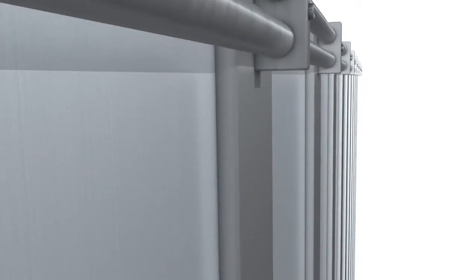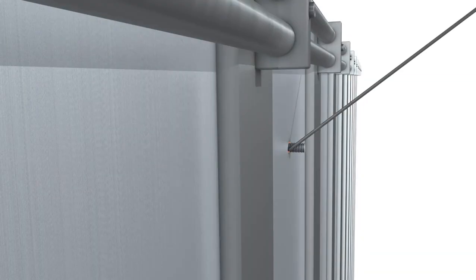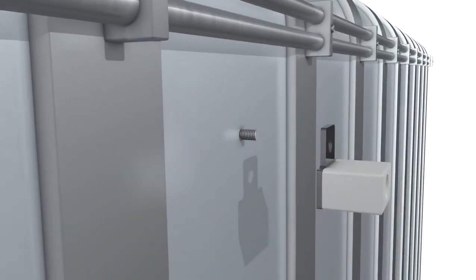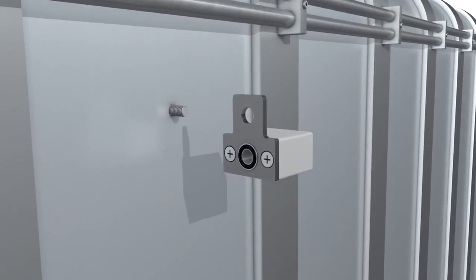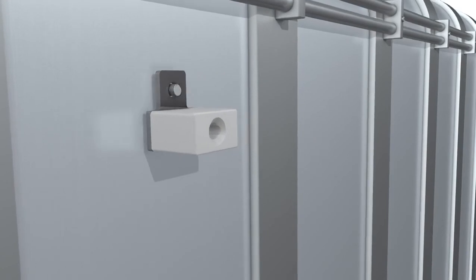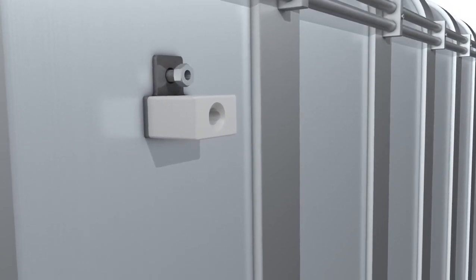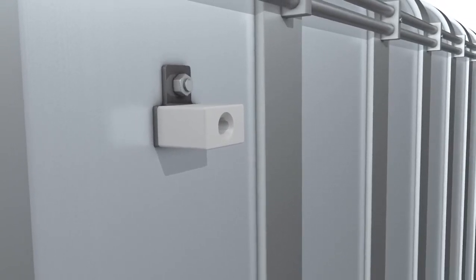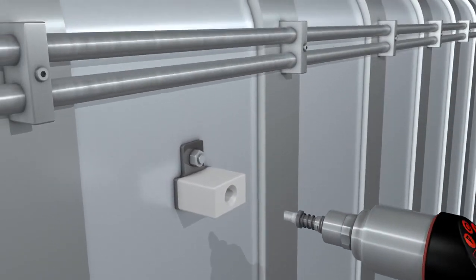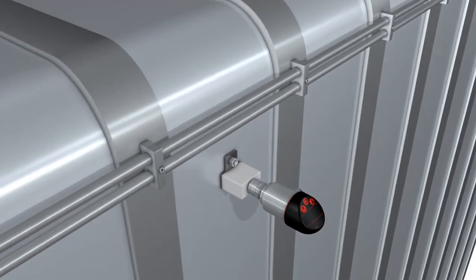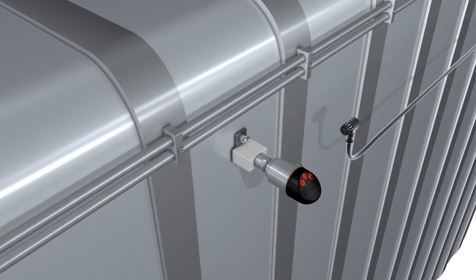A tank solution is available whereby the device is bolted to a weld stud on top of the tank wall. This easy-to-handle solution is shown here. The stud is welded to the tank, the clamp block is tightened down, and the measuring device can be inserted. For easy operation, the indication can be mirror imaged by 180 degrees to match how it is installed. The capacitive key functions match the mirror-imaged screen.